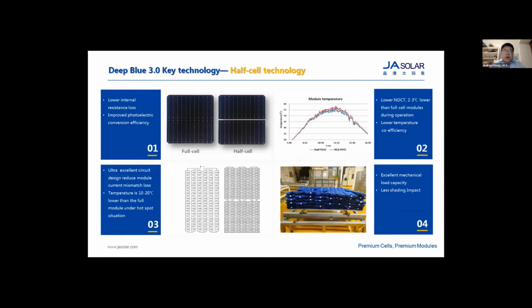The 182mm module is designed with half cells instead of full cells. This lowers internal resistance loss and module temperature during operation, with less shadow impact and mechanical stress. It also has an excellent circuit design that reduces module current mismatch loss, with temperature 10 to 20 centigrade lower, especially in hotspot situations, compared with the full cell module.